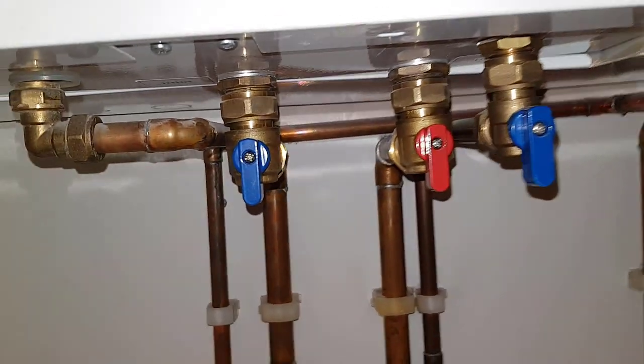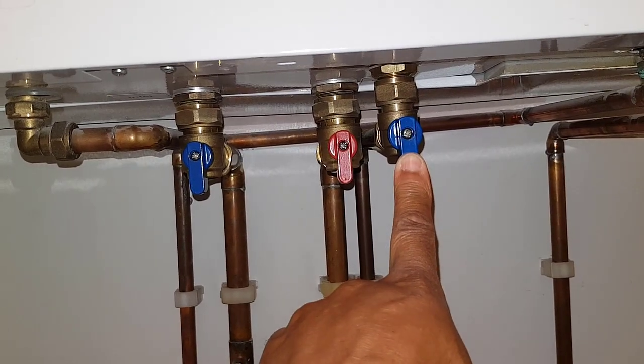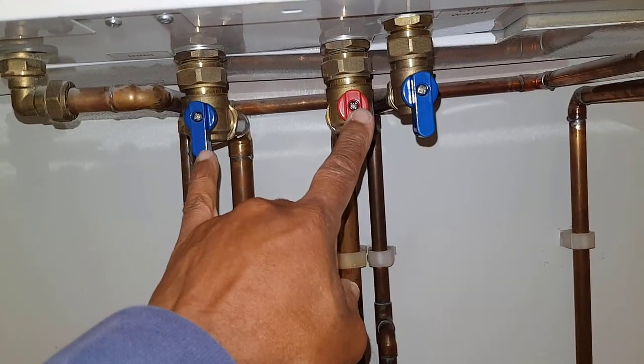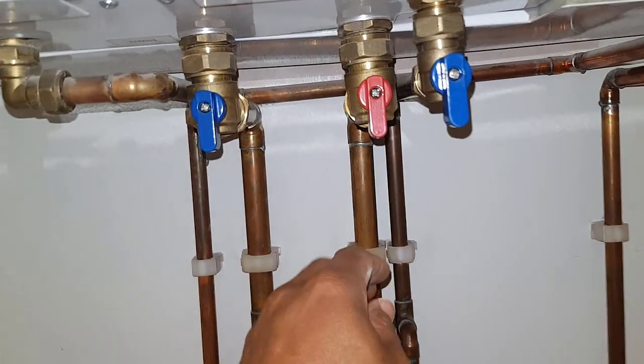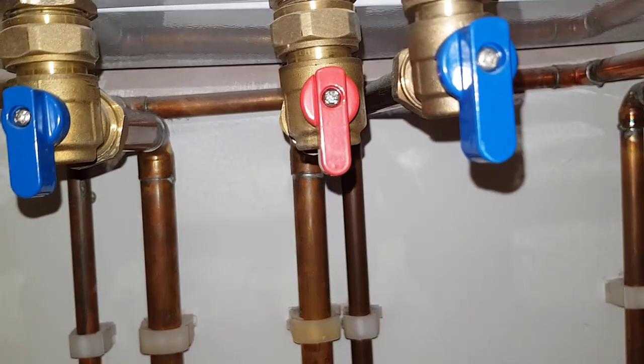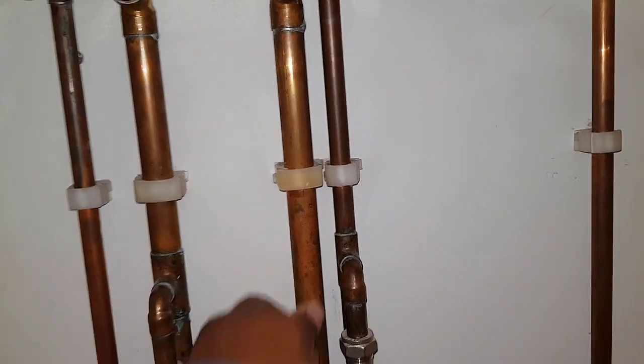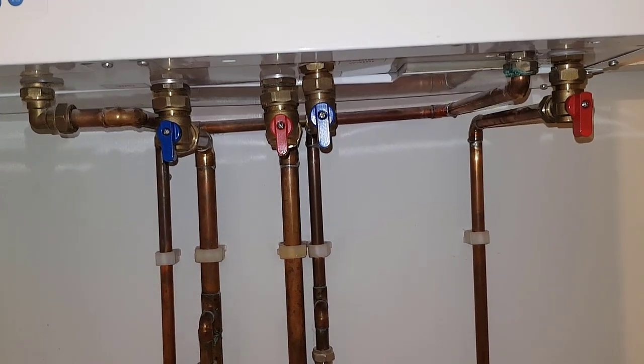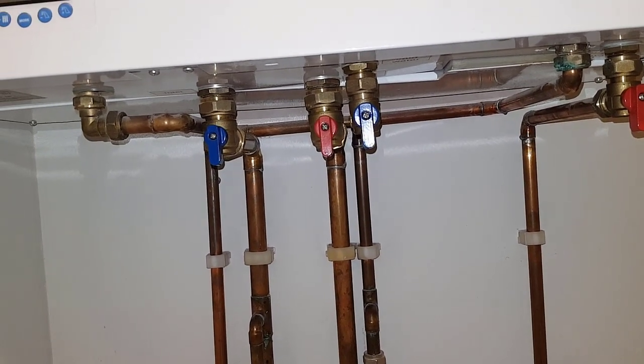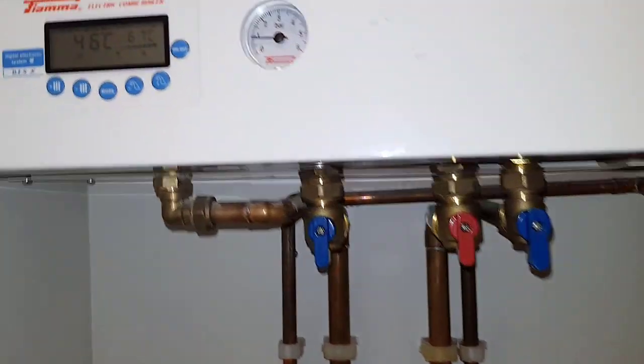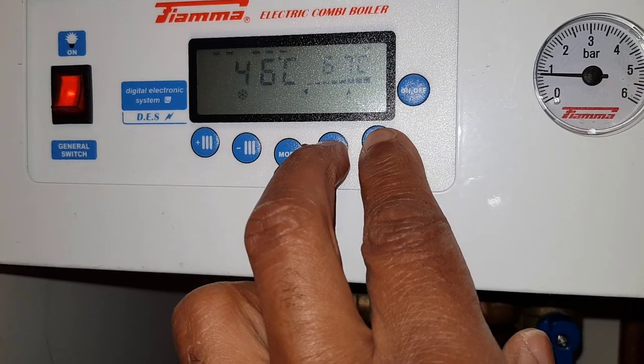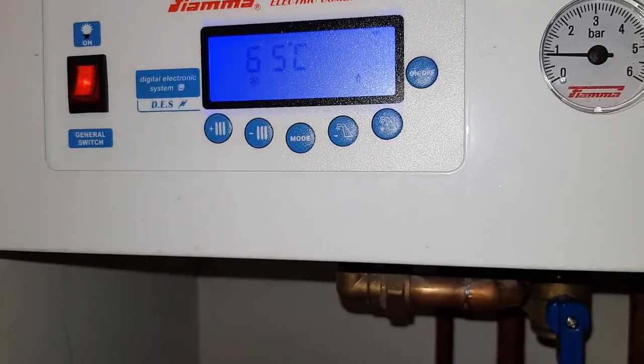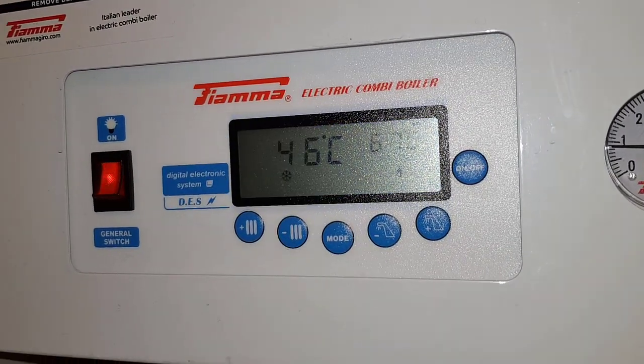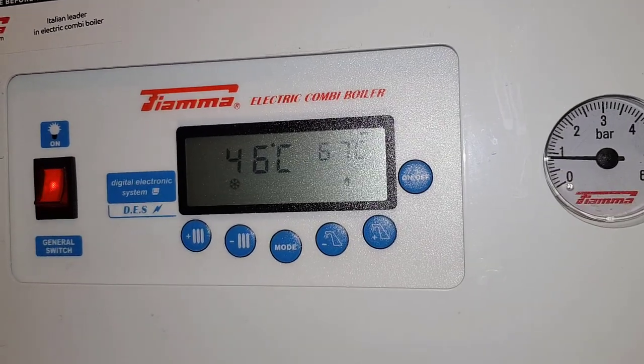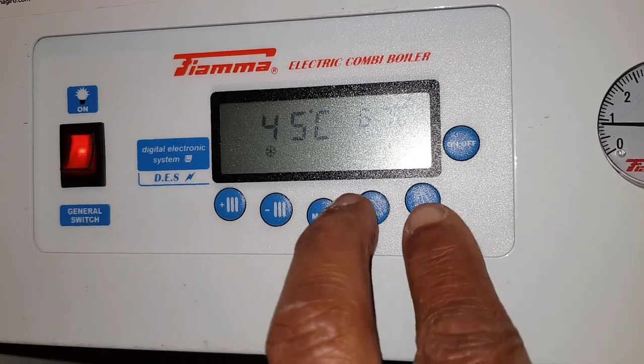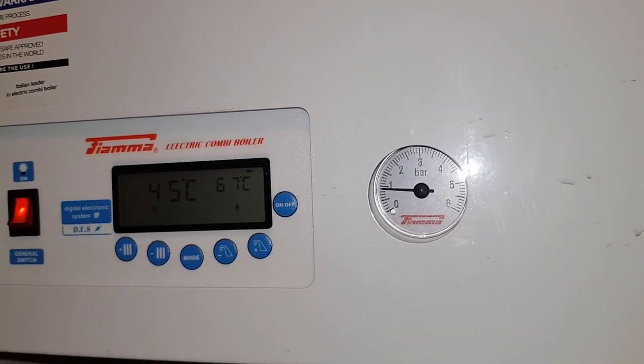What will happen now, this is the flow and return here, these two. If I feel this here, this flow is starting to get hot. So the radiators will start getting hot. That's what the customer's saying, that the heating radiators are getting hot all the time. I think what happened when we came, this was turned off like this. So you can see the pump stopped, it's gone off, but really you should have that on. You hear the pump stop now, all gone quiet.